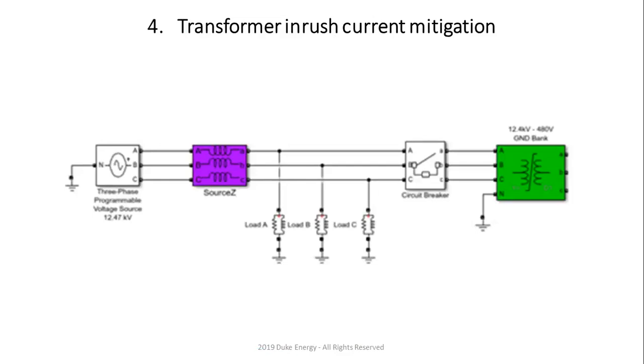So I went and simulated about 9 different things we can do, because remember, you have a 650 kVA battery and a 500 kVA transformer. That means you're going to have a whole lot of inrush current in there. So how can your 650 kVA battery potentially support something that's 7, 8, 10 times 500 kVA? So this is typical, this is what happens.